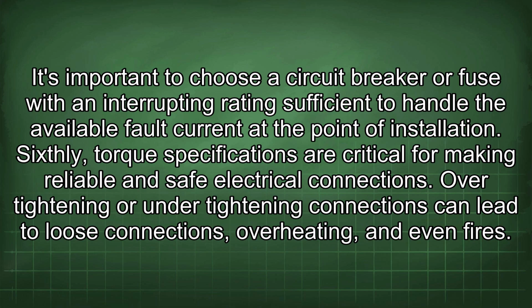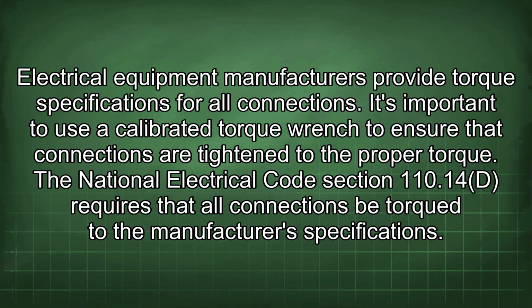Sixthly, torque specifications are critical for making reliable and safe electrical connections. Over-tightening or under-tightening connections can lead to loose connections, overheating, and even fires. Electrical equipment manufacturers provide torque specifications for all connections. It's important to use a calibrated torque wrench to ensure that connections are tightened to the proper torque. The National Electrical Code Section 110.14(D) requires that all connections be torqued to the manufacturer's specifications.